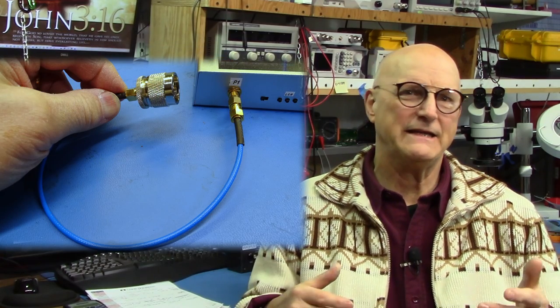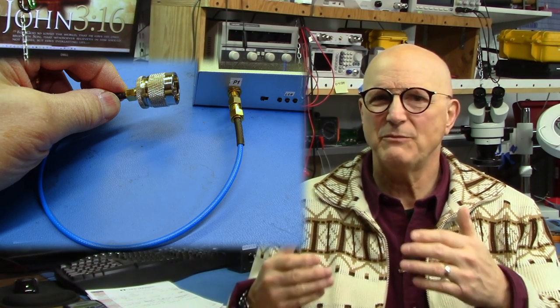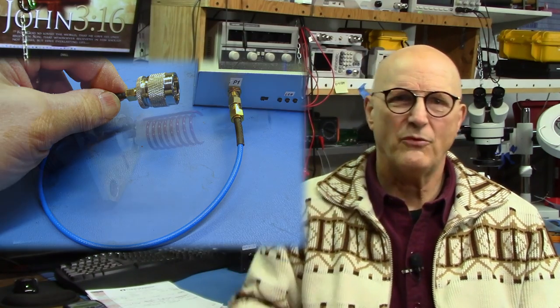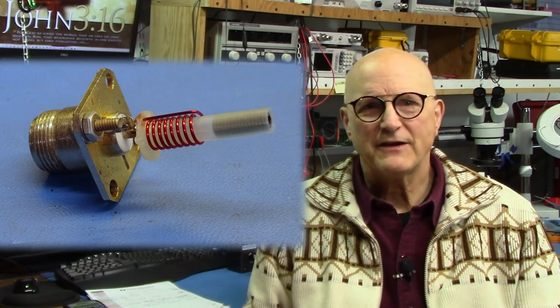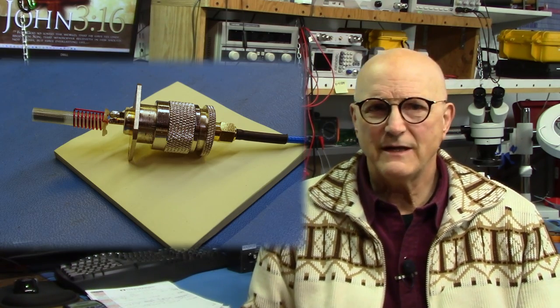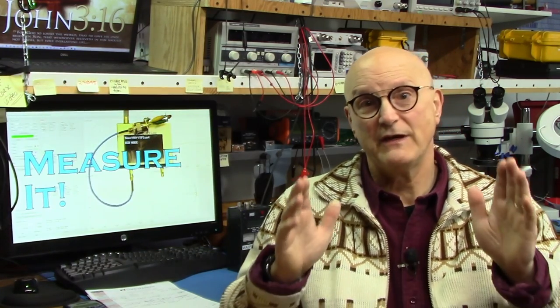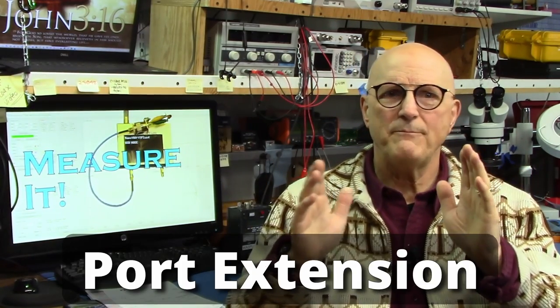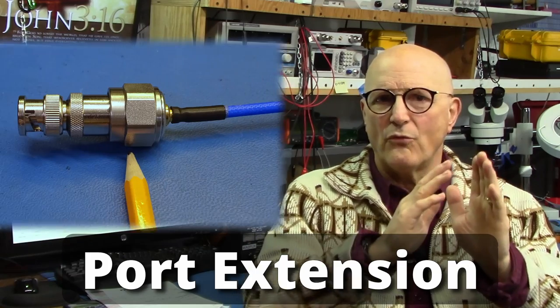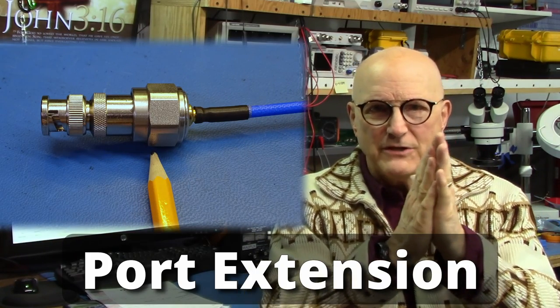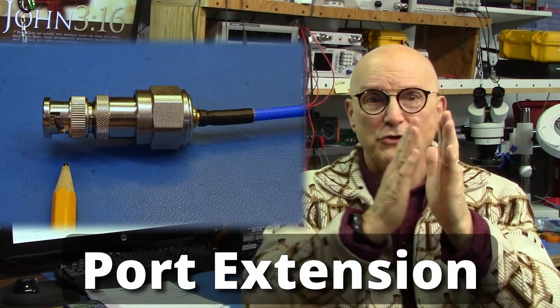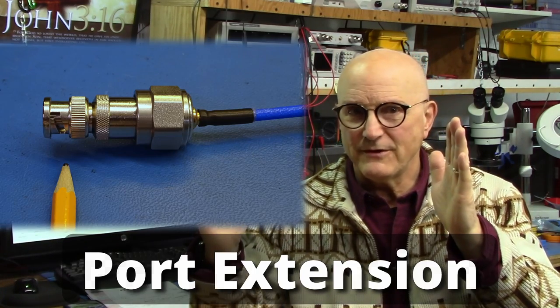and you have to add an adapter to accommodate the item to be tested. Case in point, I have this inductor on an end connector. Now I need to go through this lovely cable to an adapter so I can connect my inductor. Now, as long as the cables and adapters are all of the 50 ohm variety, we can use what's called a port extension to move the reference plane from where we did the calibration at the VNA port to the reference plane of the adapter.